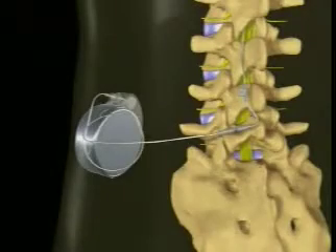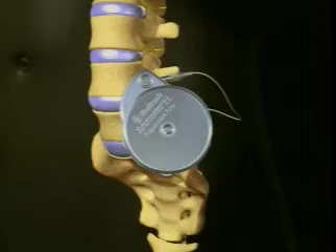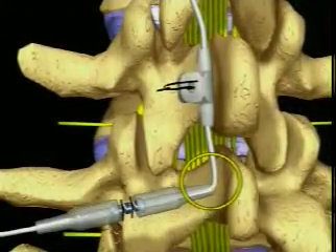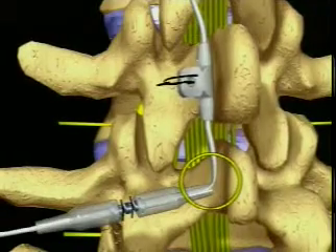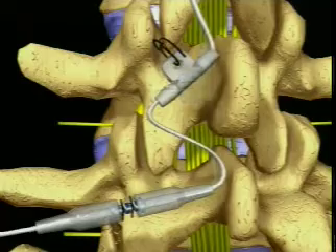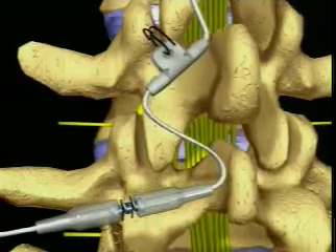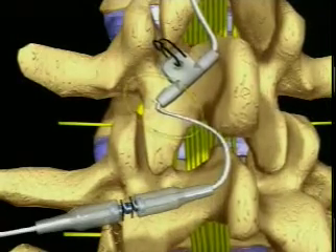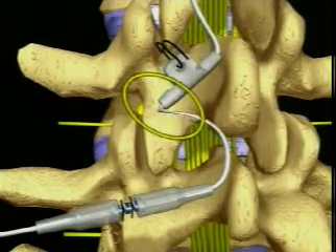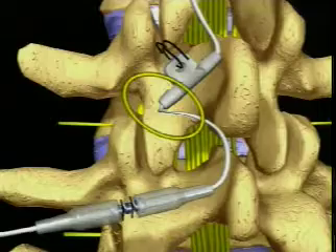Catheter kinks and occlusions can occur both at the spinal anchoring site and in the pump pocket. At the spinal anchoring site, body movements may cause a catheter to twist or kink if there is insufficient or excessive slack in the system. Kinks can also occur if the catheter and anchor are sharply angled, either due to improper anchor orientation or changes in catheter and anchor position when the incision is closed.